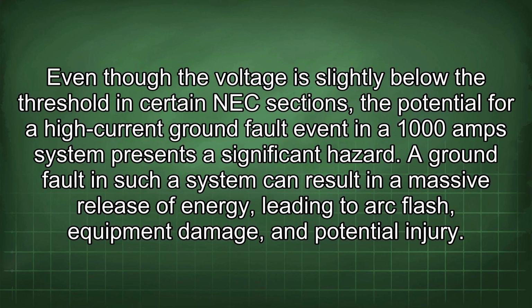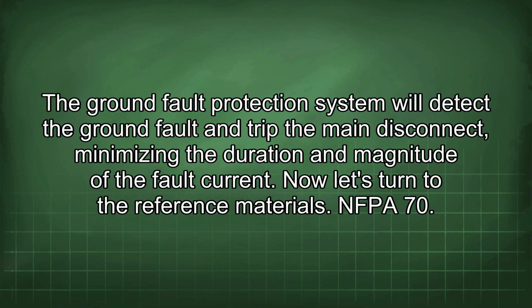A ground fault in such a system can result in a massive release of energy, leading to arc flash, equipment damage, and potential injury. The ground fault protection system will detect the ground fault and trip the main disconnect, minimizing the duration and magnitude of the fault current.